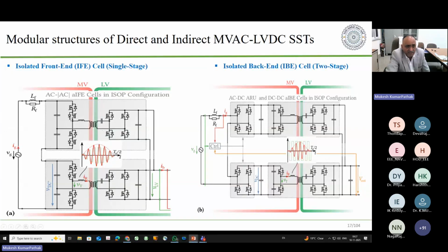On the output side, when you apply AC here, this AC would be converted into high frequency AC through these 4 devices, and applied to respective transformer primaries. The secondary side would be a control rectifier plus inverter, so this would be converted to 50 Hertz output, and they are in parallel. So you can see this is a structure where the modularity is there, and this is a direct AC to AC conversion.